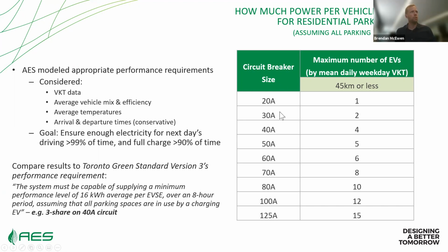What the model solves for is basically how much sharing you can do on a branch circuit of different amperages, while ensuring households have enough electricity for the next day's driving 99% of the time, and are fully charged at least 90% of the time. This table shows, for a given average VKT, the maximum number of EVs that could share branch circuits of given sizes.